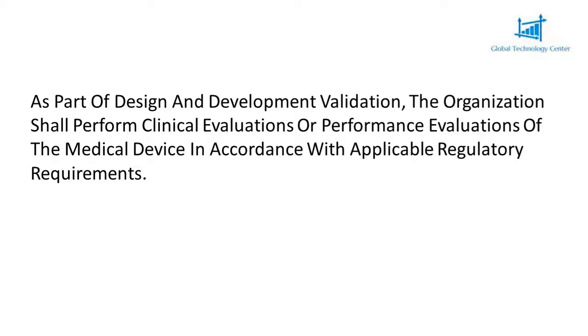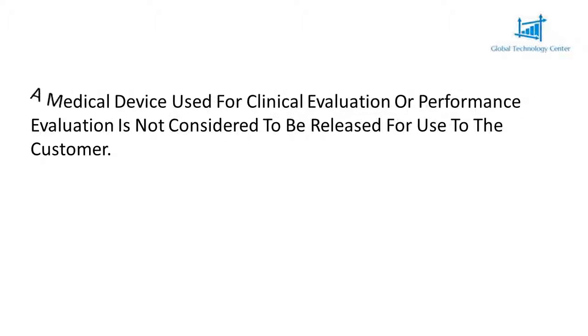As part of design validation, the organization shall perform clinical evaluations or performance evaluations of the medical device in accordance with applicable regulatory requirements. A medical device used for clinical evaluation or performance evaluation is not considered to be released for use to the customer.